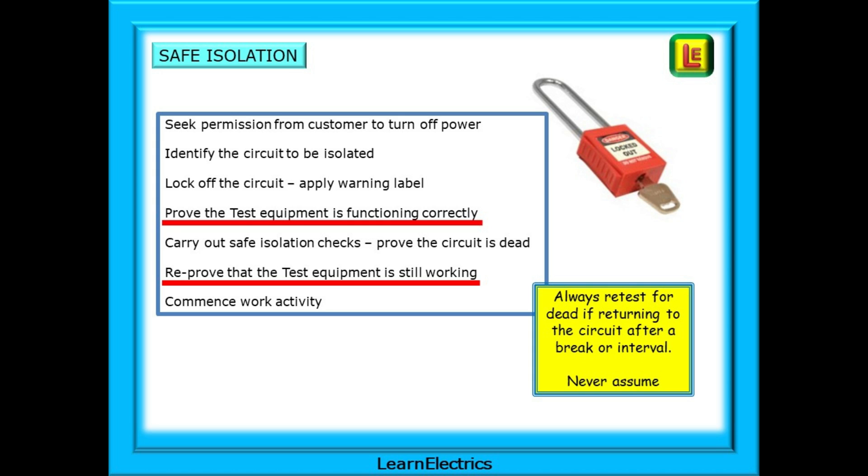Identify the circuit to be isolated, and then lock off the circuit and apply a warning label. Prove the test equipment is functioning correctly, and then carry out safe isolation voltage checks to prove that the circuit is dead. Reprove that the test equipment is still working, and then commence the work activity. It cannot be stressed enough that you should always retest for dead if returning to the circuit after a break or interval. Never assume that all is still dead. You don't know if someone has turned the power back on or bypassed your lock, and it does happen.